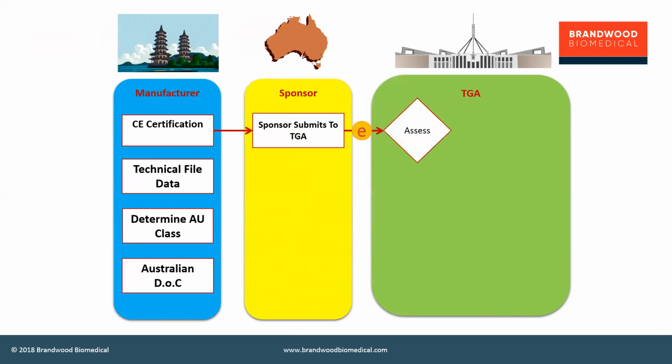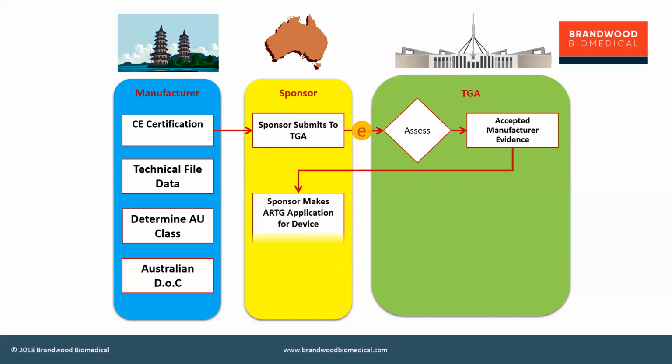The CE certificate is passed to the sponsor, who then submits it online through the e-business system to TGA, who verify the authenticity of that certificate. And once that is done, that is considered to be accepted manufacturer evidence, and it's entered onto TGA's manufacturer database. At that point, the sponsor can then come back and make applications for registration of any device within the scope of that certificate manufactured by the holder of that certificate.